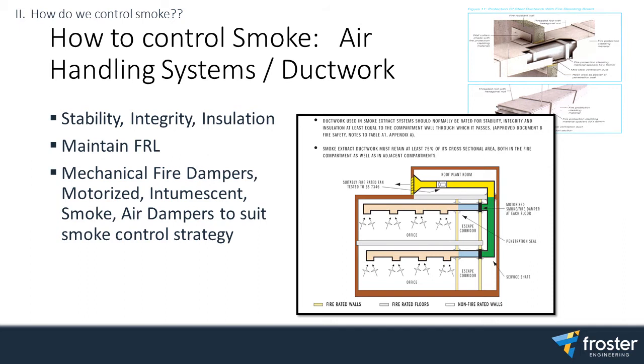Because if there's a breakout in fire in that ceiling and these supports go, say that's a 5 or 10 meter run, then that duct is going to collapse. The weight of that duct is going to pull that damper off the wall. So you're meant to have a break on the damper connection with ductwork. So that's something that I would have to inspect, something that you should also be aware of when you're walking around site. It should have a slip joint connection. Because again, you don't want to lose the integrity of your smoke control. Putting all the effort into the design and construction of it, that one little item could compromise it.